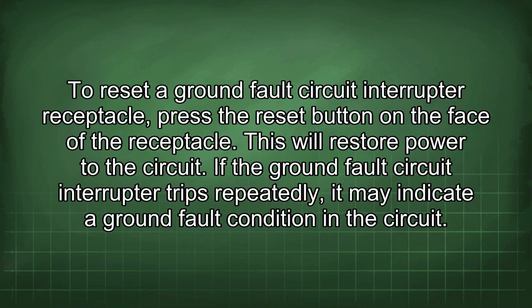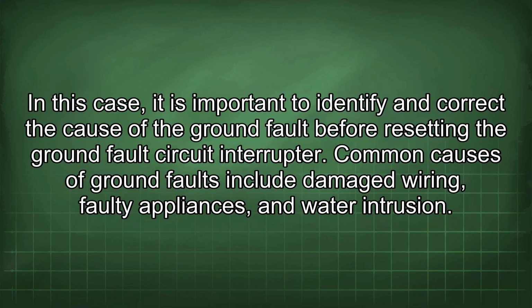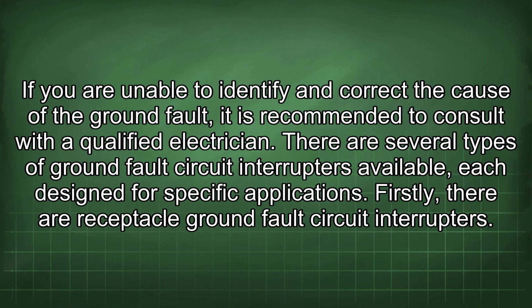To reset a ground fault circuit interrupter receptacle, press the reset button on the face of the receptacle. This will restore power to the circuit. If the ground fault circuit interrupter trips repeatedly, it may indicate a ground fault condition in the circuit. In this case, it is important to identify and correct the cause of the ground fault before resetting the ground fault circuit interrupter. Common causes of ground faults include damaged wiring, faulty appliances, and water intrusion. If you are unable to identify and correct the cause of the ground fault, it is recommended to consult with a qualified electrician.